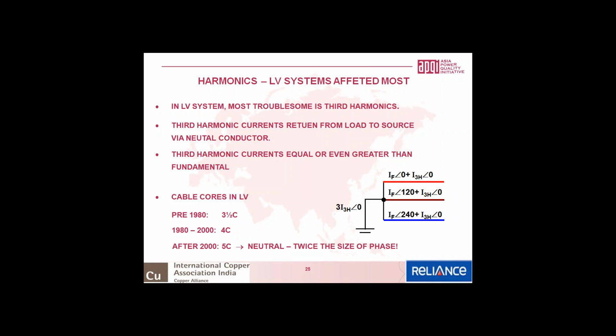After the 1980s until 2000, when electronic equipment started getting introduced at the low voltage level, we went for a 4 core cable, where the neutral is the same size as the phase. After 2000, with the proliferation of sophisticated electronic equipment, we are now going for 5 core, where the neutral is twice the size of the phase.